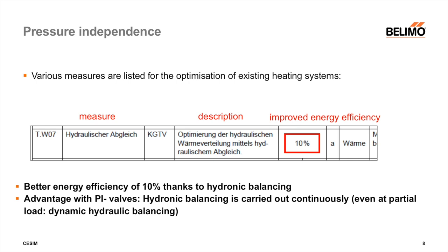With hydronic balancing carried out not only statically, but also dynamically at partial load by pressure-independent control valves, energy saving and improved energy efficiency of 10% can be achieved. That means with our electronic pressure-independent valve, we can save 10% of energy by having a dynamic hydraulic balancing.